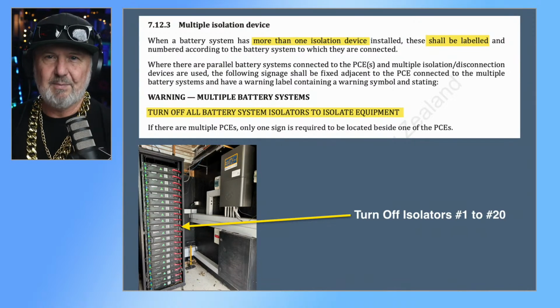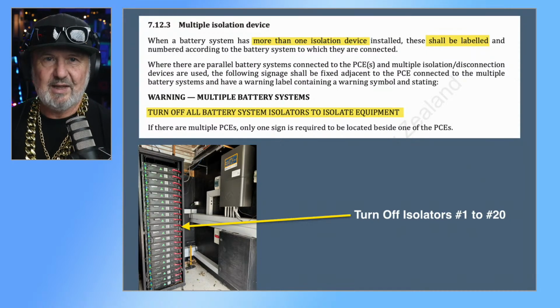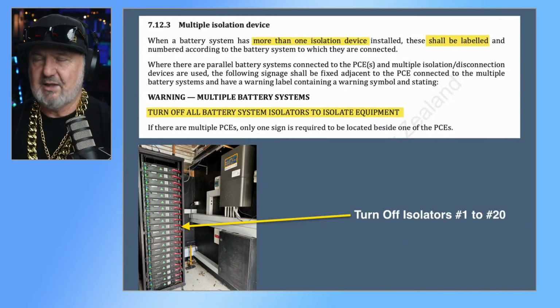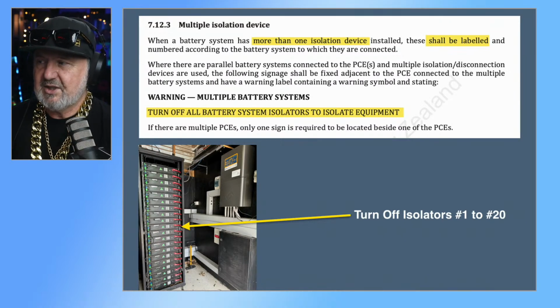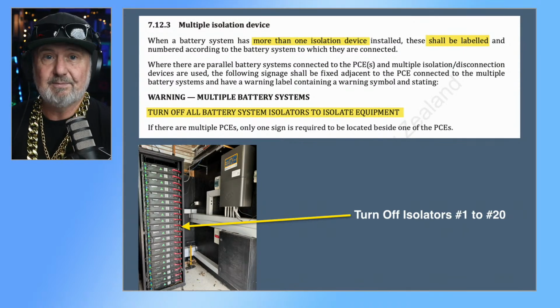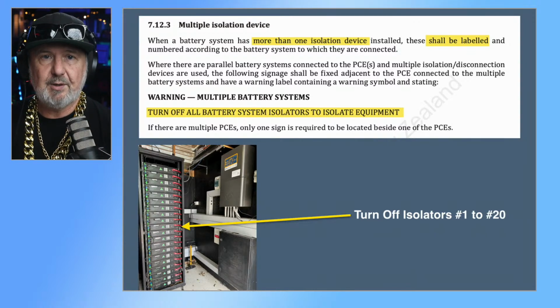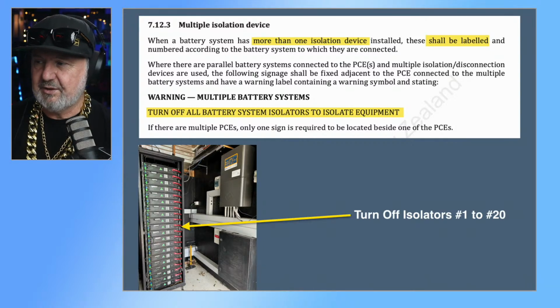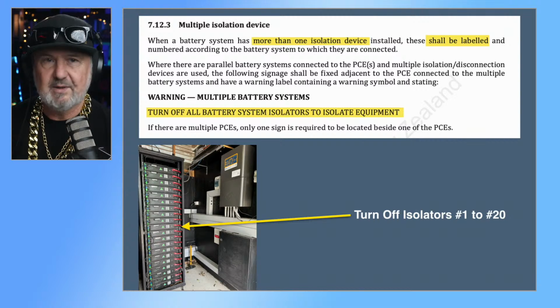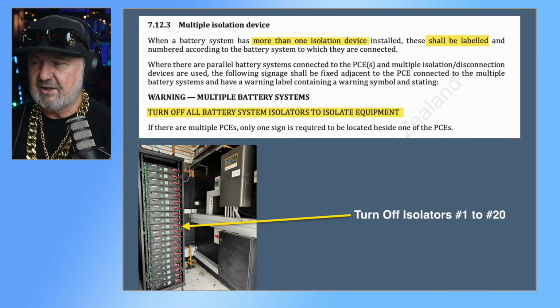Someone said, well, you're going to need a great big isolator for that whole system. But the standard actually gives you an out clause, and it says you can have multiple isolation devices for the battery system. When a battery system has more than one isolation device installed, these shall be labeled. So by labeling, you can have many points of isolation. In this case, each of the circuit breakers on each of the Power Plus Energy batteries is effectively an isolator. It's also overcurrent protection. It's double poled, load breaking under fault, and therefore it's an isolator as well. But you have to specify that in the shutdown procedure. So it should say turn off isolators 1 to 20 to isolate this battery system. And you've also got to have that warning sign, warning multiple battery systems. Turn off all battery system isolators to isolate this system.